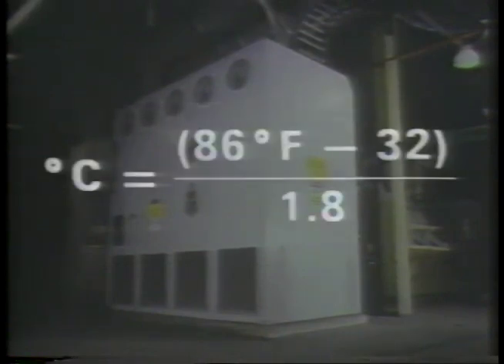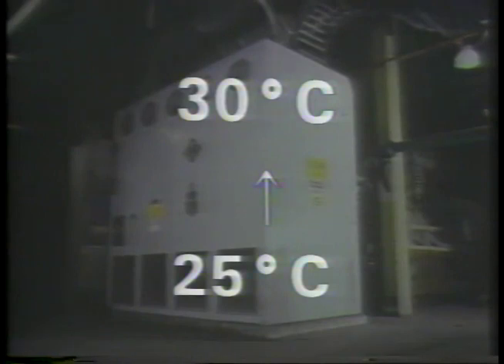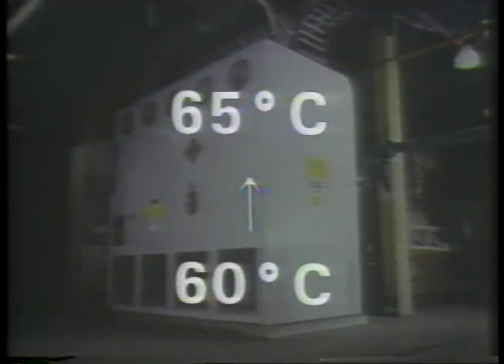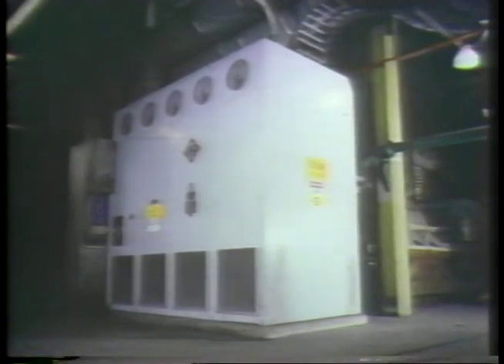To convert 86 degrees Fahrenheit to Celsius, we subtract 32 from 86 degrees Fahrenheit and divide by 1.8. We get 30 degrees Celsius. Ambient temperature rose 5 degrees Celsius, from 25 degrees Celsius to 30 degrees Celsius. So we would expect that the transformer temperature would rise from 60 degrees Celsius to 65 degrees Celsius, and not to 69 degrees Celsius, which we might think if we didn't convert ambient temperature to degrees Celsius.